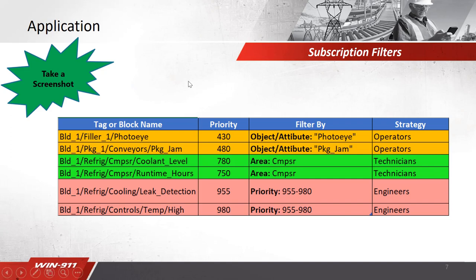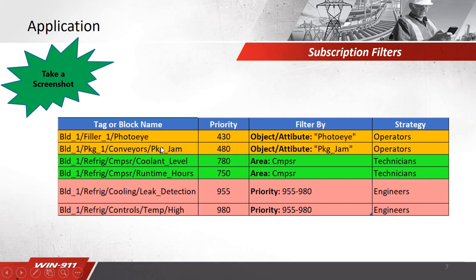First, you'll have to understand which alarms you want to notify on and who you want to send those alarms to. You'll take a look at the alarms you have and see that we want to notify on object attribute for photo eye and packaging jam. So we're looking right here, photo eye packaging jam for those object attributes. And who do we want to send these to? We want to send these to the operators. So I create an operator strategy this will go to. That strategy then points to a tactic or a call-out list of people.